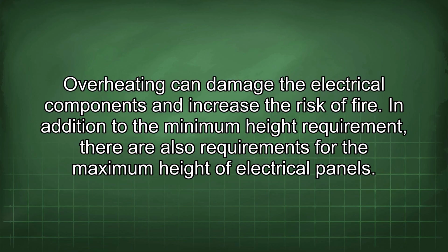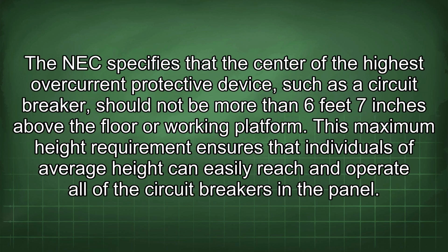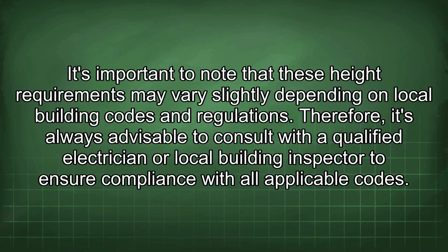In addition to the minimum height requirement, there are also requirements for the maximum height of electrical panels. The NEC specifies that the center of the highest overcurrent protective device, such as a circuit breaker, should not be more than 6 feet 7 inches above the floor or working platform. This maximum height requirement ensures that individuals of average height can easily reach and operate all of the circuit breakers in the panel. It's important to note that these height requirements may vary slightly depending on local building codes and regulations. Therefore, it's always advisable to consult with a qualified electrician or local building inspector to ensure compliance with all applicable codes.